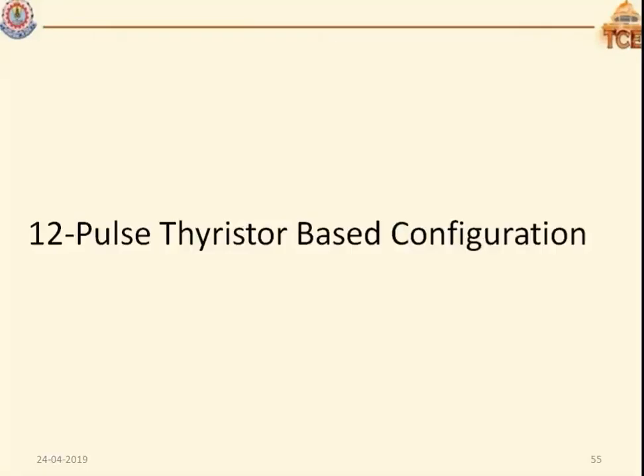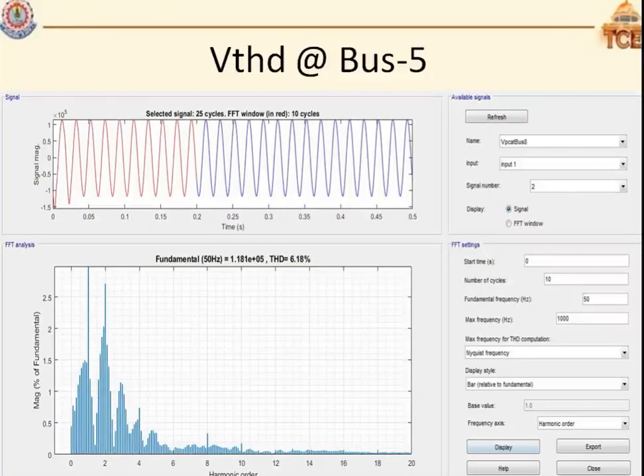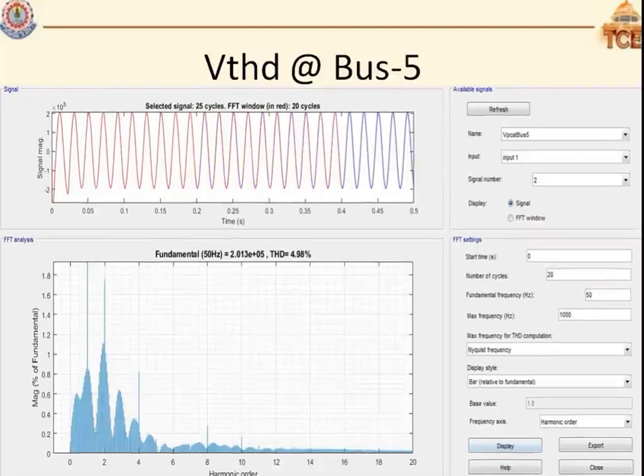You can see the results. This is the 12 pulse thyristor based configuration. Next, the beauty of the DC arc furnace technology is that when we feed it with the DC converter supply, we can easily predict the harmonics nature, because during 6 pulse we can calculate the harmonics such as 6p plus or minus 1, fifth order, and third order or seventh order.